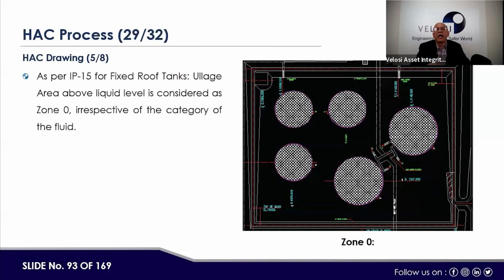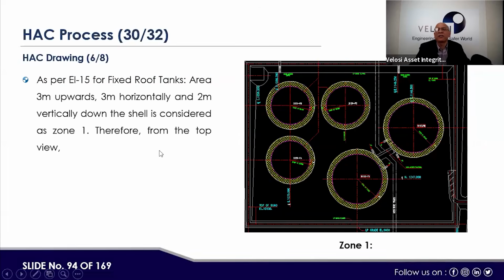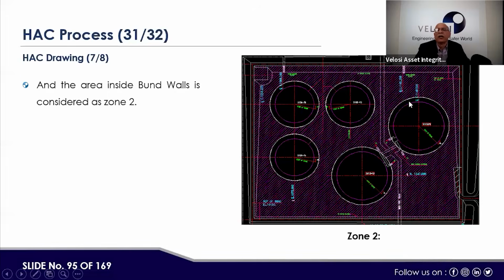Now, inside the plant area, we have done zone 0 marking because there's fluid inside the tank. So the dotted area is zone 0. Next, this area, about 3 meters or 2 meters as per the standard, we have marked as zone 1. Then the areas outside zone 0 and zone 1 are zone 2 areas up to the dikes, right? So any electrical or instrumentation equipment installed inside the plant has to meet the zone 0 requirement, then the zone 1 requirement, and the zone 2 requirement.